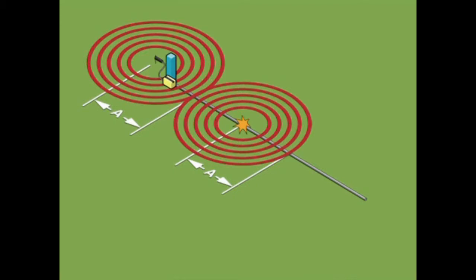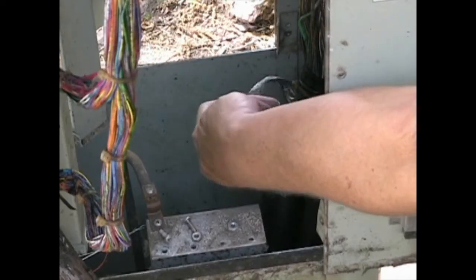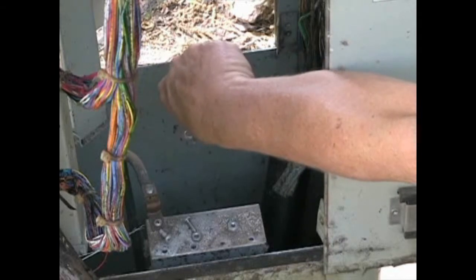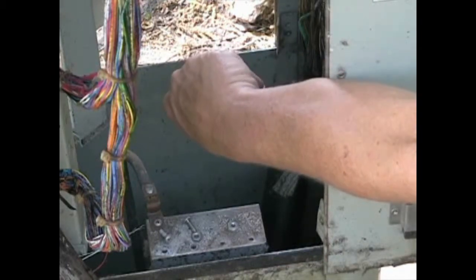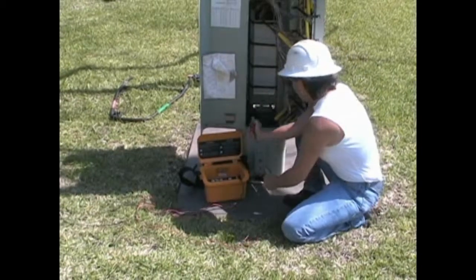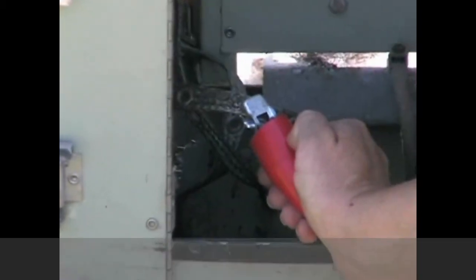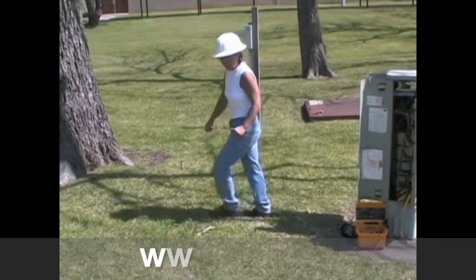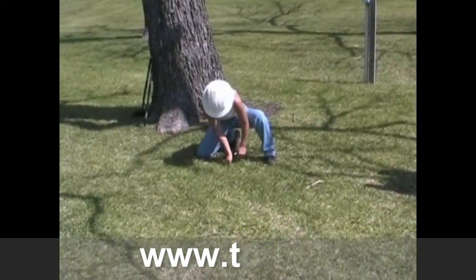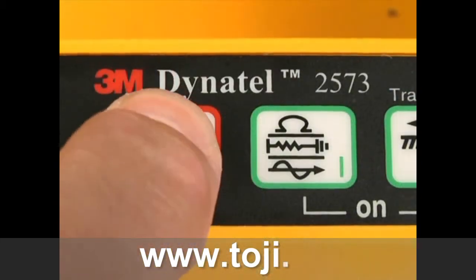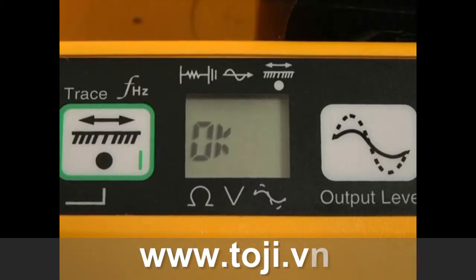To measure the severity of the fault on this conductor, first ensure that both ends of the faulted conductor are open or isolated from any connection. Connect the red lead of the transmitter to the faulted conductor. Place the ground rod behind the transmitter in line with the suspected path of the conductor. Connect the black lead of the transmitter to the ground rod. Check the battery level of the transmitter by holding down the off key.